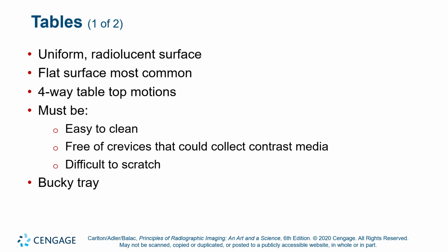Flat surface is most common. Philips did a weird thing where they had raised edges down the longitudinal edges of the table. Yeah, that was not a good idea. It was an uneven work surface. When you try to do extremity work, that raised edge always gave you fits because you couldn't lay your cassette flat. It was always canted and sloping from left to right. So a flat surface is ideal.